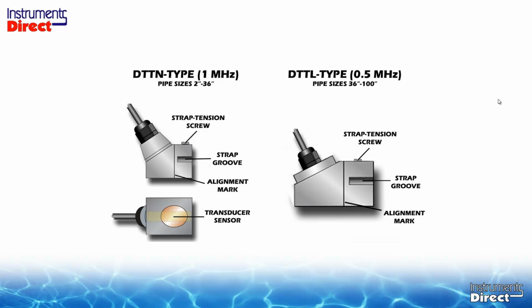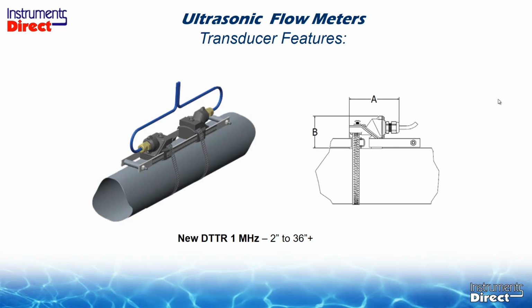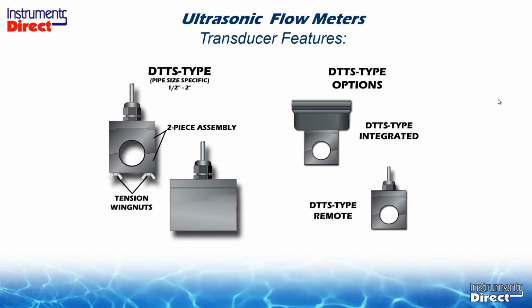The DTTL is a 0.5 megahertz sensor, traditionally used in pipe sizes 36 inches and larger, or for smaller pipes that have poor pipe wall conditions. Now, the small pipe sensor, the DTTS, is for pipe sizes 0.5 to 2 inches and is not adjustable. It is pipe size specific and material specific.